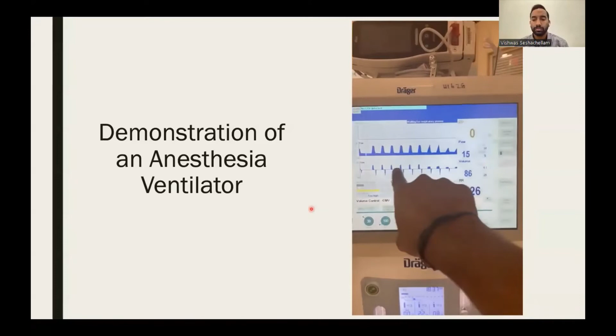So if I want to change this, I have a Pmax, the maximum pressure that's detected until an alarm sounds here. I can change this. So I can say I don't want to exceed 15. And I won't exceed that pressure of 15. This is where I altered the pressure, the tidal volume will decrease. So now if I deliver this, it still won't exceed that. But it'll say tidal volume not achieved because it's set to stop at that pressure of 15 here. Now if I want to deliver a higher tidal volume, simply increase this to 250.